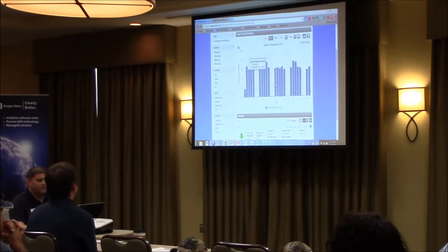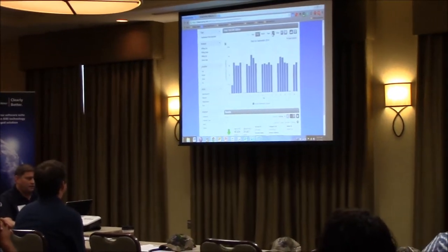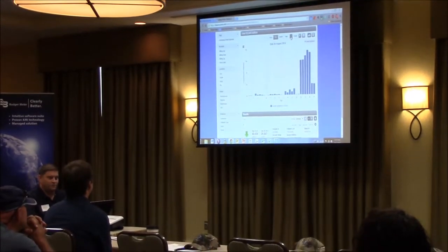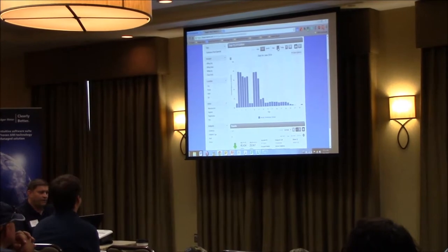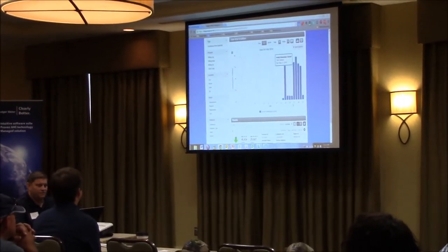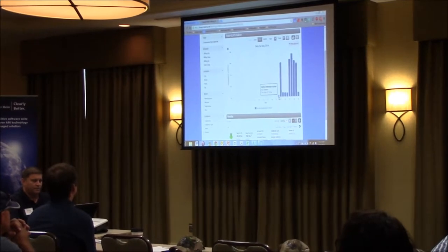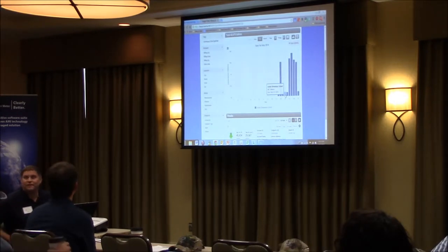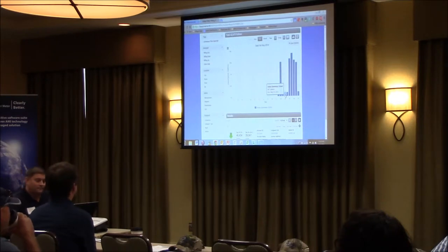They've got a very normal weekday pattern, and you can tell when school started. There was a little bit of usage before school started through the summer. But when you go back to the end of last year, this was put out on May the 22nd. You notice right here, this is a Sunday: 870 gallons used by that school on a Sunday.